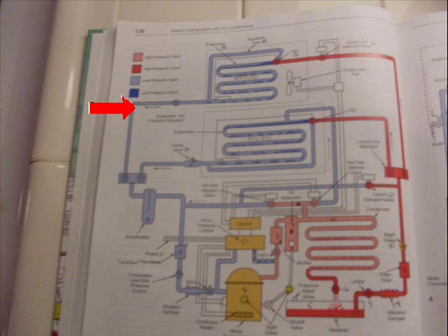Now you're going to hear these definitions multiple times in the next 2 weeks. You are going to get them always a little bit differently. You said it's a pressure regulator until the pressure in the evaporator. Pressure and temperature, right? Not temperature. Just pressure. Just the pressure overcomes the spring setting, right, and the refrigerant gets to leave. Yeah, I thought I heard you say temperature. Well, it creates a higher temperature. Well, it does. But the valve only works on pressure. It's a pressure operated valve. But when you have a higher pressure, you create a higher temperature. Right. But the valve doesn't work on the temperature. It just works on the pressure.